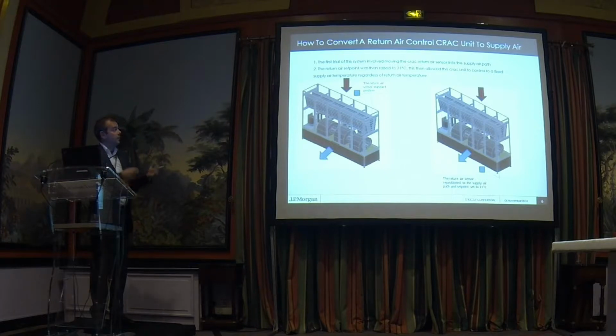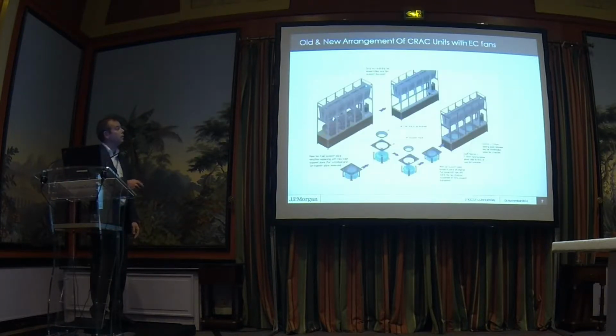So back to the return air supply air. Basically, you just get the sensor at the top, stick it in the bottom, set it at 21, and off you go, just as a trial to see how much your air conditioning will back off. This is a bit of a wrong picture, it's got a DX in it. Our unit, you can't do this on DX, you've got to do it on chilled water. So, the next thing we came up with is, let's get rid of these belt-driven motors, 3 belt-driven motors in there with a 4 kilowatt motor each.